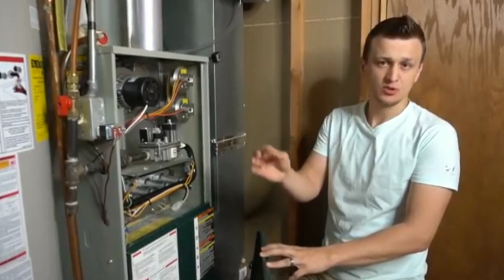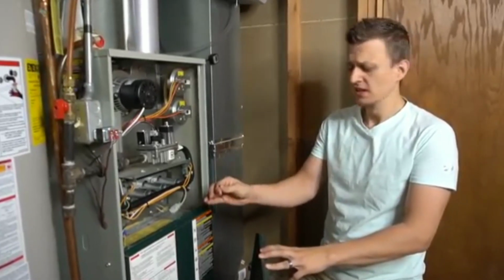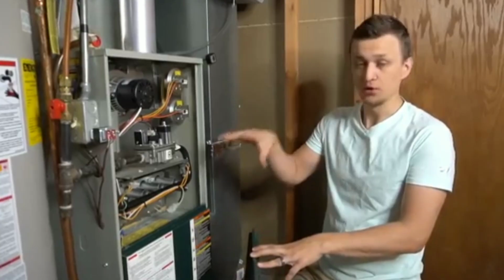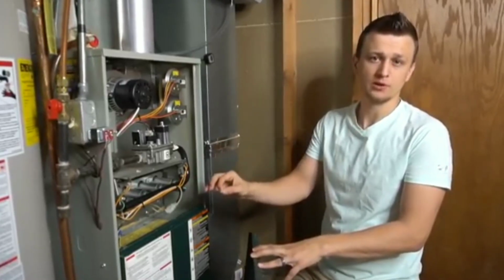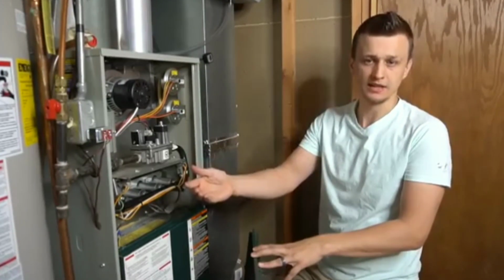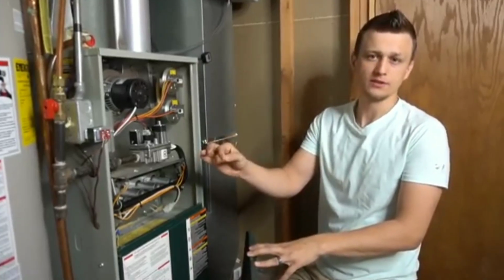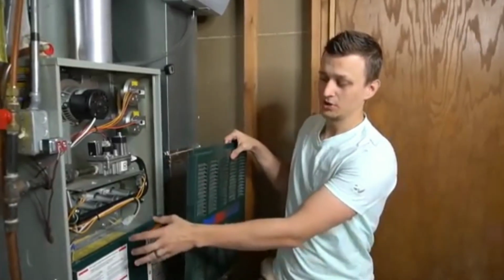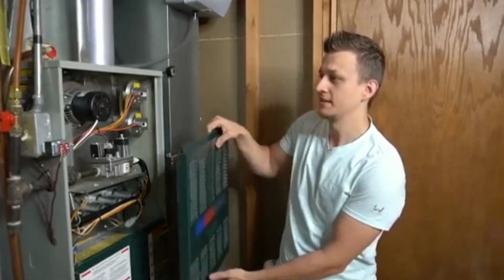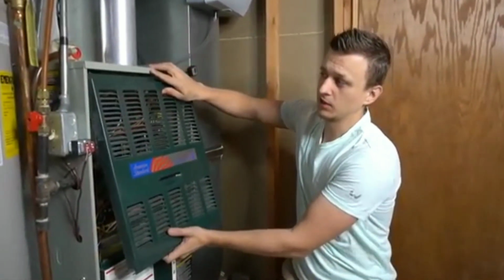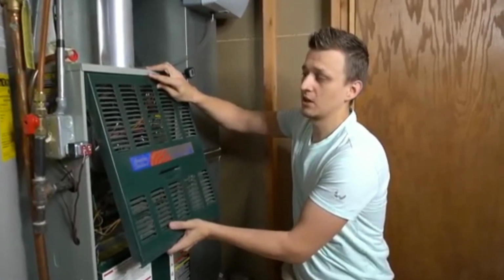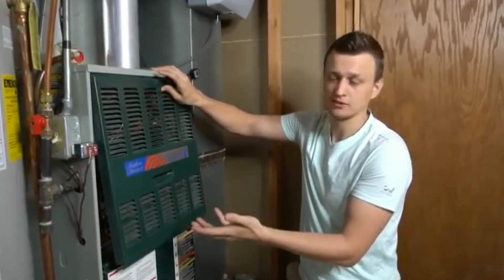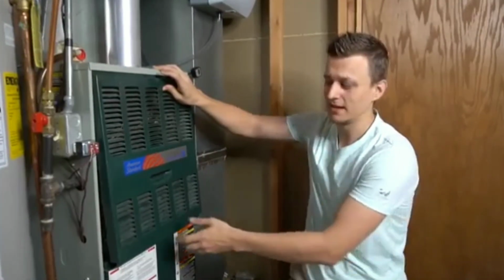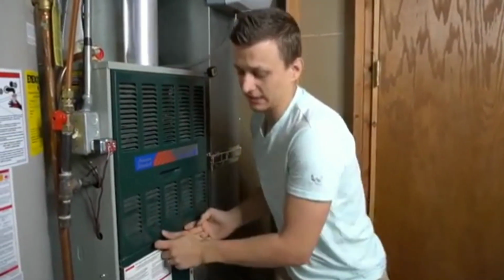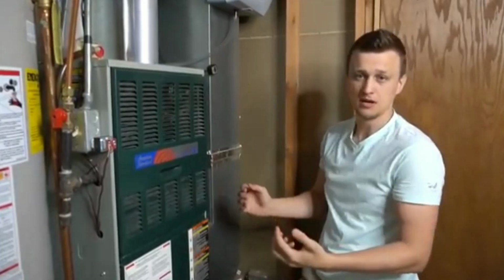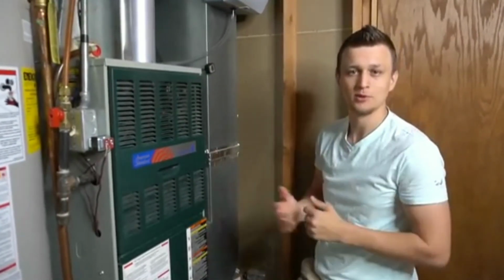And I do get asked, do we need to oil that blower motor? And the answer is no. Unless you have a really old furnace, you do not need to oil that motor. It comes permanently lubricated, so there are no oil ports where you can oil it. And just a fair warning, some of these doors come off a lot easier than they come back on. Once in a while I'll get an order to go to somebody's house just to put the furnace doors back on, because somebody took them off and they're not able to put them back on. So when you're taking your doors off, do pay attention to how they come off so you can put them back together in a similar fashion.